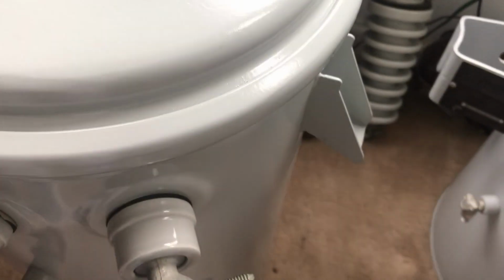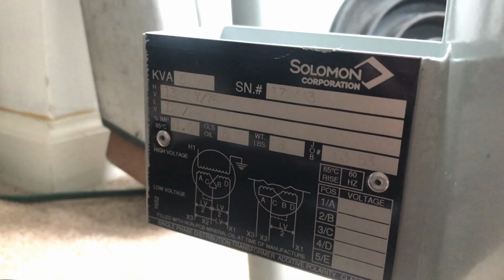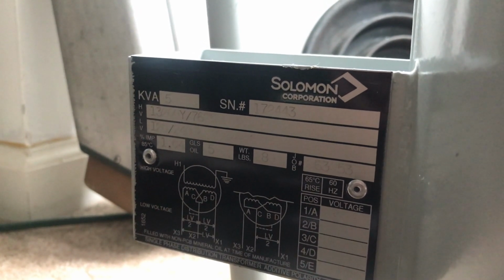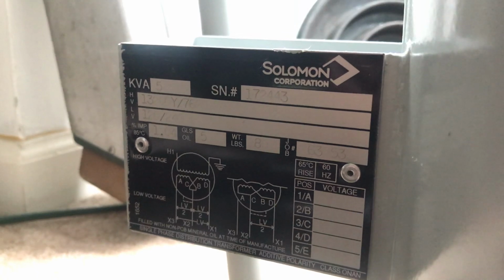Now, let me spin this around, and bear with me because it weighs more than twice as much as me, but I'd like to show the specifications plate. As you can see, the high voltage is rated at 13,200 Y 7620. This is for a 13.2 kV system. The reason why the coil of the transformer only sees 7,620 is because of the square root constant, in which I'll do a diagram later just to visually show how that works.